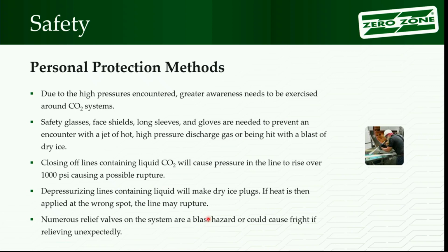Same thing can happen if you have liquid and vapor, but not as dramatically. As long as there's liquid and vapor present, it's going to continue to follow its pressure-temperature chart, and the pressures are going to rise, getting you up over 1,000 pounds. So again, possible damage to the equipment or the piping, or you could have a relief valve release CO2, and then you have to bring a bottle over and recharge it. When you depressurize the line and drop below 60 psi, you generate dry ice. That's why you have dry ice when you go to the store. It sits on the table. We usually talk about it in training, set it at 100 pounds because it's an easy number to remember.